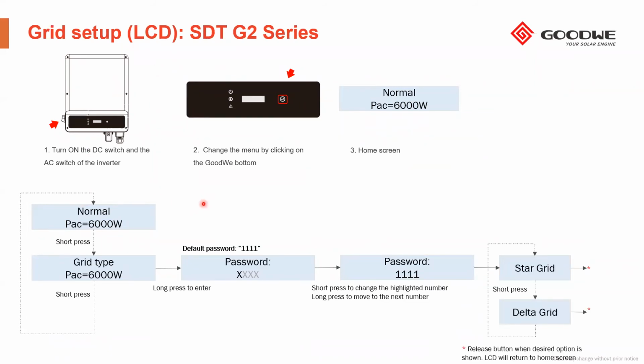As long as we are talking about the C&I, we can set up the inverter depending on the grid we are connected to, as star or delta. So we select the menu grid type, a long press, we include the password - this is for protection, for safety - second level menu, and then we will be able to select star or delta.